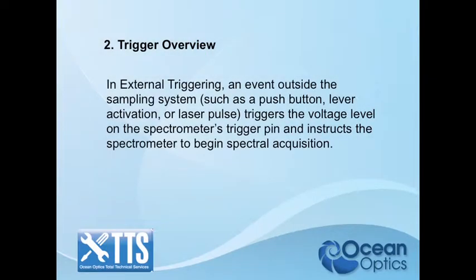A trigger is an event outside the system — which in this case is our spectrometer — that is going to make it do something. Either a push button, a lever activation, a laser pulse, whatever is sent to the spectrometer to tell it to wake up. That's what the triggering does.